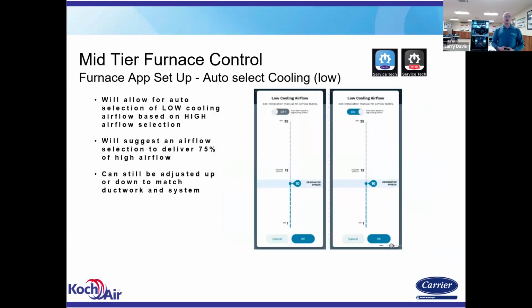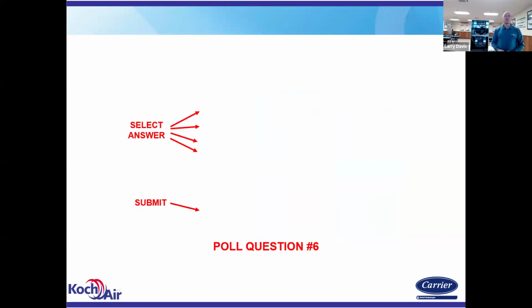Again, on your low cooling, same thing. You can set it yourself, or you can let the system set it. As of right now, it's going to load on a 2-stage outdoor unit. Low stage is about 75% capacity. So the board's going to, if you leave it for automatic, the board's going to set the airflow for about 75% of what the high speed or the regular high cooling is.